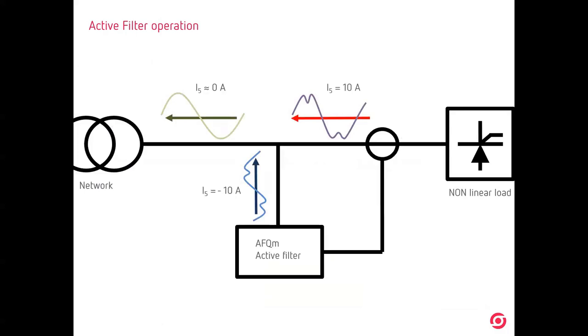Well, how the filter works very fast. Imagine that we have a non-linear load, okay, which is injecting 10 amps of the fifth harmonic. Well, the active filter will read, so you need a current transformer, obviously. We will read the current, okay? And we will inject the same current in the opposite way. It means 180 degrees, okay? In the opposite, in order to eliminate this harmonic, to erase these 10 amps of harmonic current, okay? Obviously, we want to reach zero value.